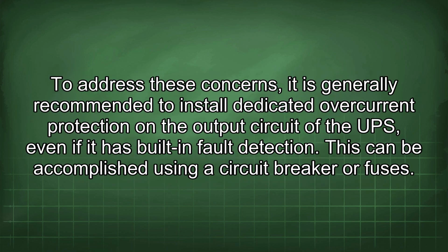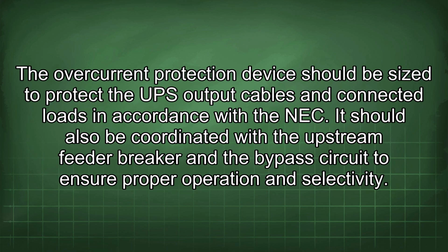To address these concerns, it is generally recommended to install dedicated overcurrent protection on the output circuit of the UPS, even if it has built-in fault detection. This can be accomplished using a circuit breaker or fuses. The overcurrent protection device should be sized to protect the UPS output cables and connected loads in accordance with the NEC. It should also be coordinated with the upstream feeder breaker and the bypass circuit to ensure proper operation and selectivity.